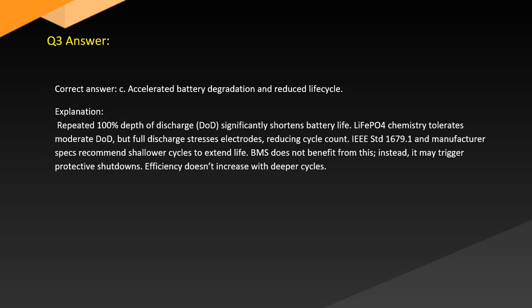Answer. Correct answer. C. Accelerated battery degradation and reduced life cycle. Explanation. Repeated 100% depth of discharge (DOD) significantly shortens battery life. LiFePO4 chemistry tolerates moderate DOD, but full discharge stresses electrodes, reducing cycle count. IEEE Std 1679.1 and manufacturer specs recommend shallower cycles to extend life. The BMS does not benefit from this. Instead, it may trigger protective shutdowns. Efficiency doesn't increase with deeper cycles.